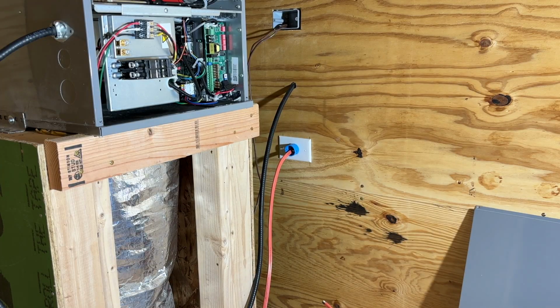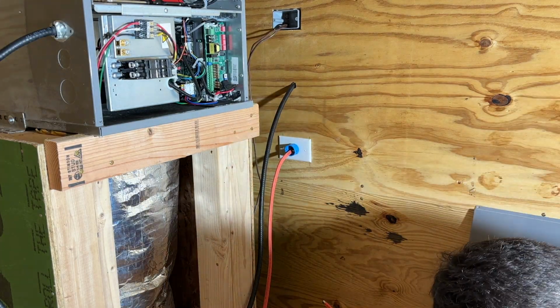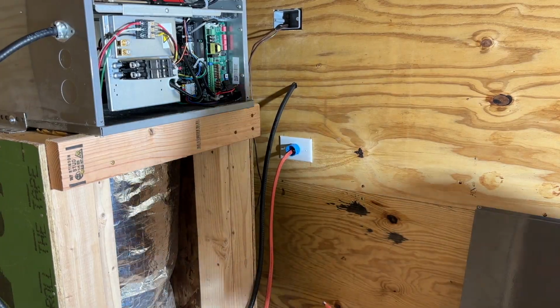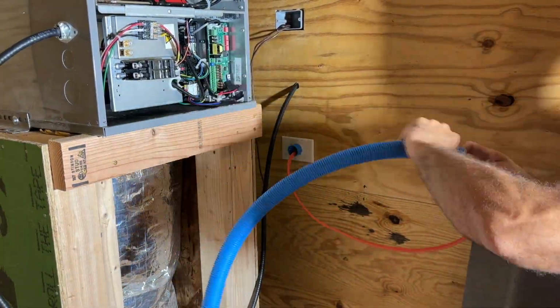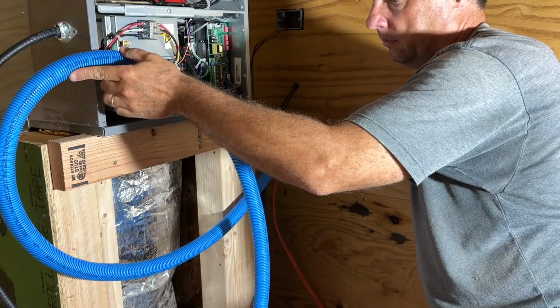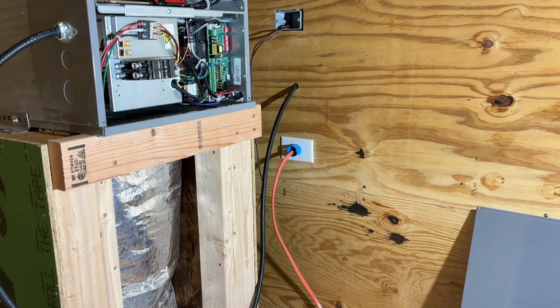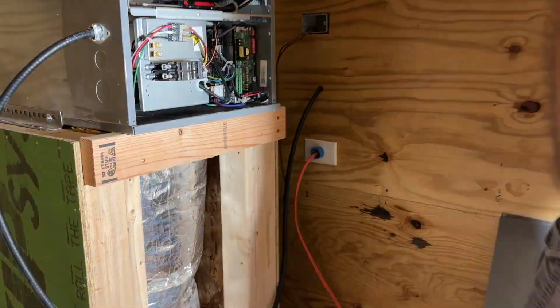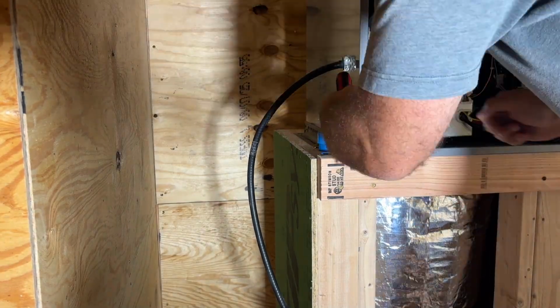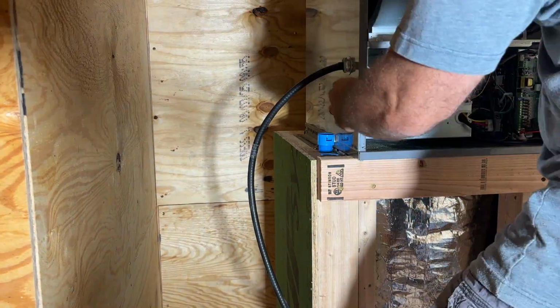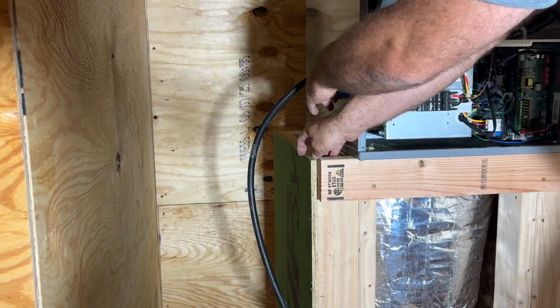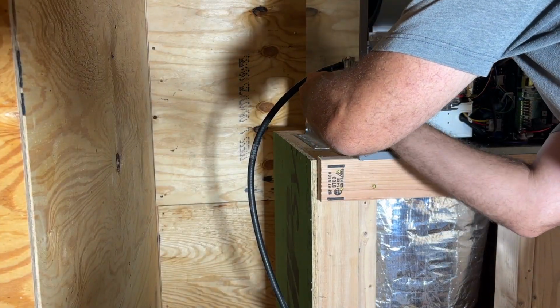It is allowed by code as I read code. You can put Romex in conduit in dry locations if you properly size your conduit not to exceed the fill calculations allowed by code, and you leave that outer jacket on. So don't strip the outer jacket off and then stuff it into your conduit. That's not kosher. Shouldn't do that.